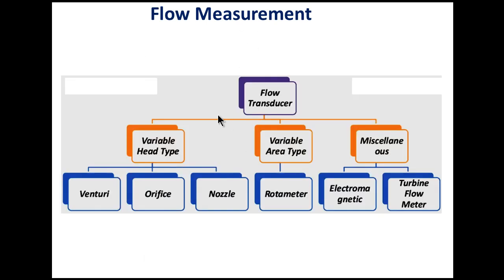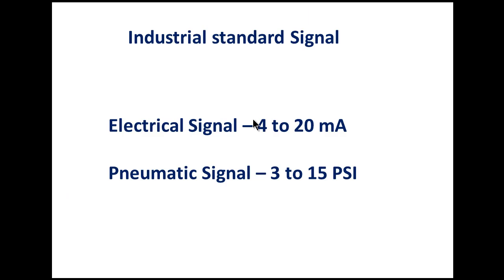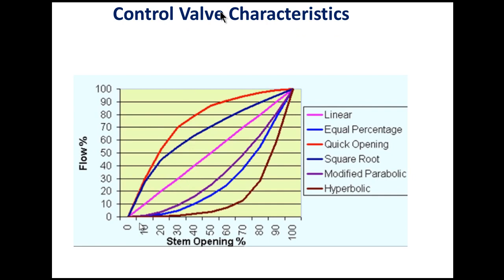Flow measurement types: variable head type (venturi tube, orifice, nozzle), variable area type (rotameter), and miscellaneous (electromagnetic flow meter, turbine flow meter). Types of flow: inferential, mass flow, and volumetric flow. Volumetric flow unit is meter cube per second; mass flow unit is kg per second. Inferential flow is defined as flow proportional to the square root of pressure. Industrial standard signals: electrical signal 4–20 mA or pneumatic signal 3–15 psi.